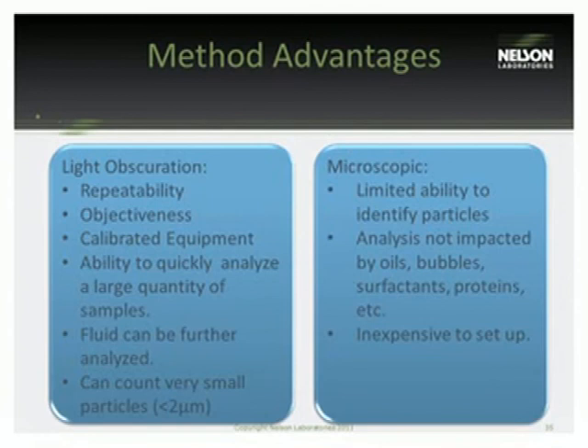Now some information on some method advantages, kind of switching gears a little bit. The light obscuration method is the preferred method by the USP, and most regulatory agencies also like to see the light obscuration method used first with a device, or with any testing for that matter, in particulate testing. Probably the most important reason for that is the repeatability and objectiveness of the light obscuration method. The light obscuration method uses a liquid particle counter, which is a calibrated piece of equipment. It's non-biased, it's repeatable, and so regardless of who is testing, regardless of the technician, you're going to get pretty consistent results from the light obscuration method.